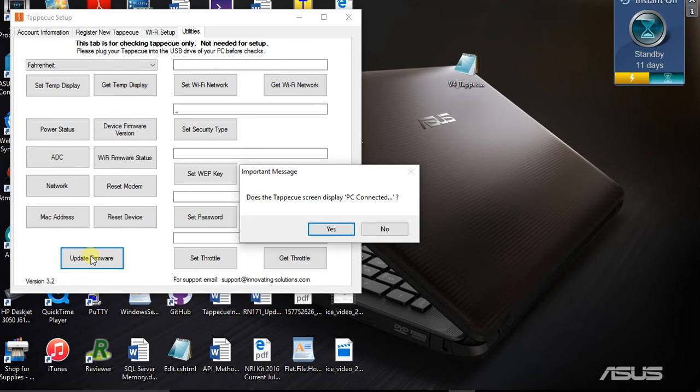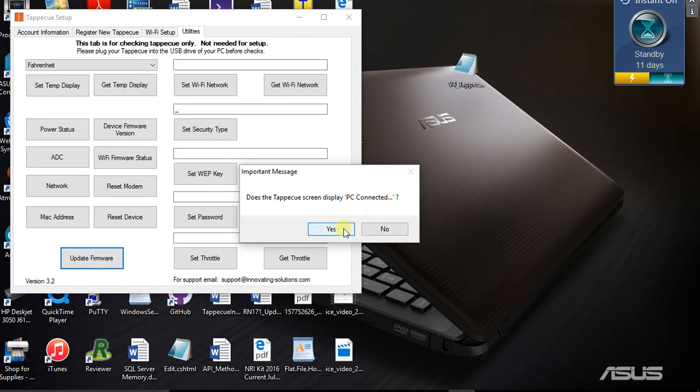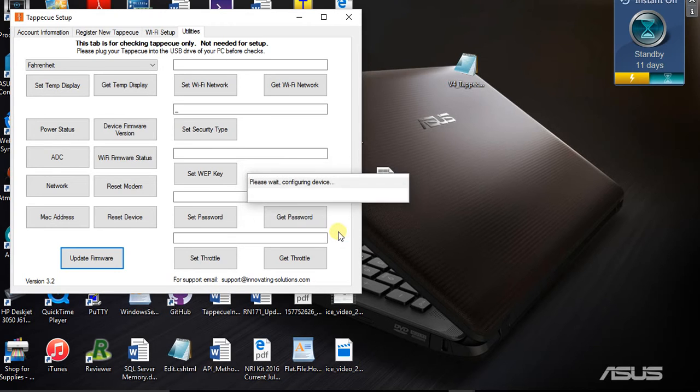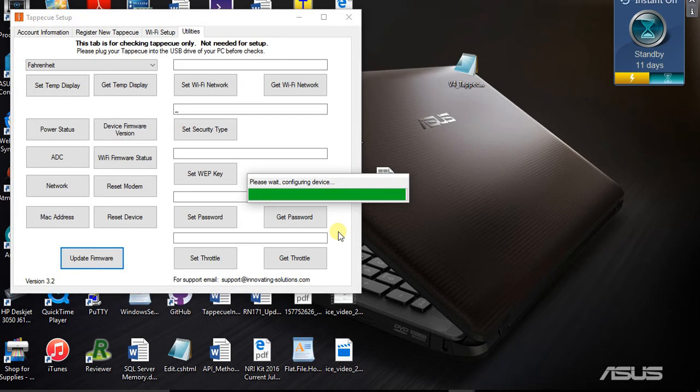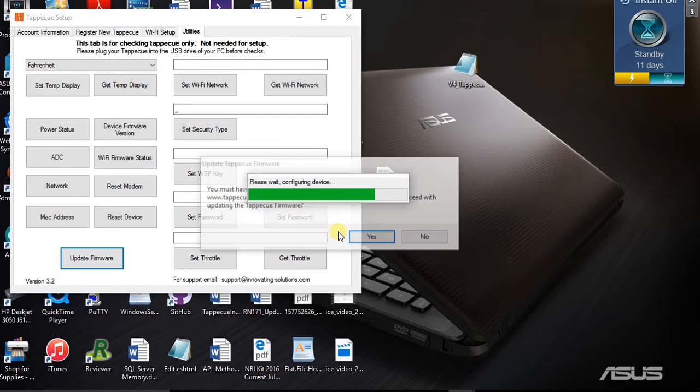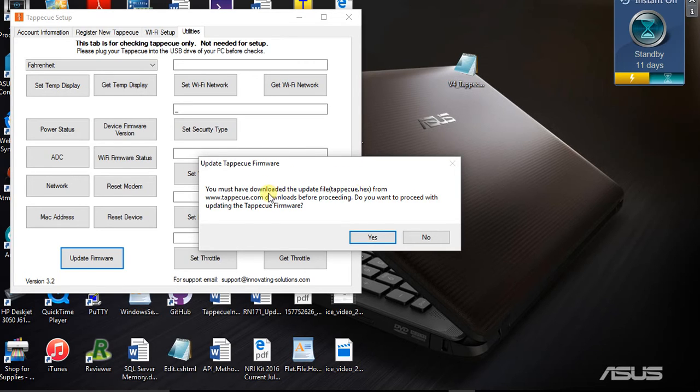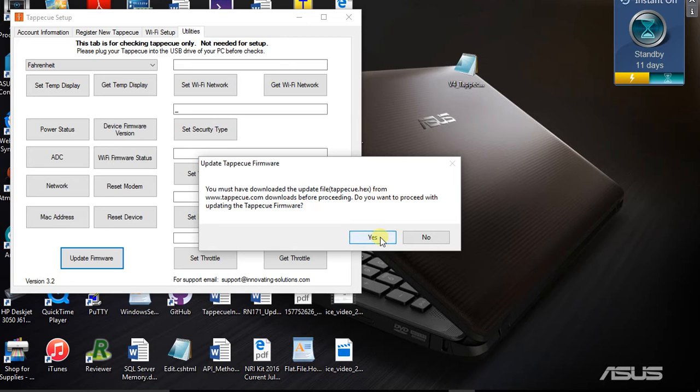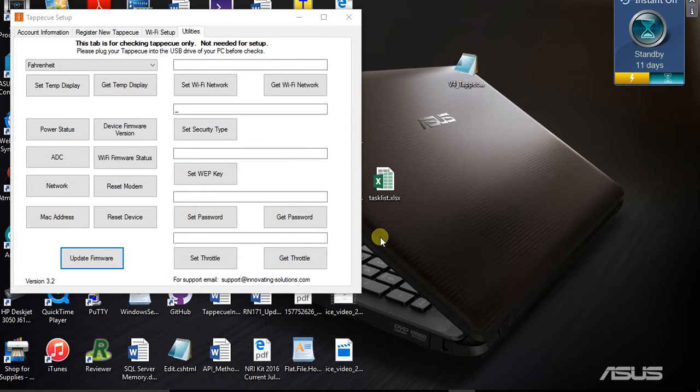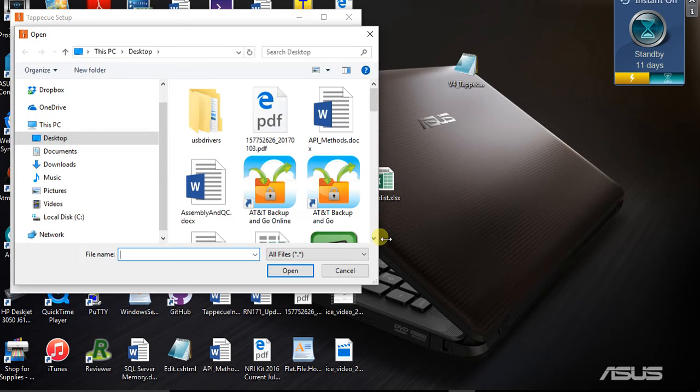I'm going to do the update firmware. Does the Tappecue screen display PC connected? If you look over at your Tappecue, it should tell you PC connected. Say yes. What it's doing right now is verifying that you don't already have the latest firmware. If you do, it would give you a note saying you already have the latest firmware, no need to update. Since mine doesn't, it says have you downloaded the Tappecue hex file. Yes, we downloaded it.